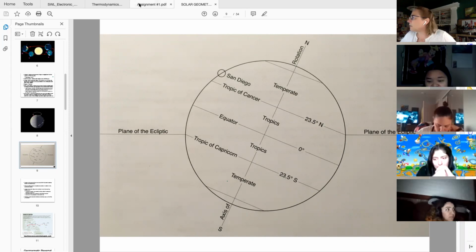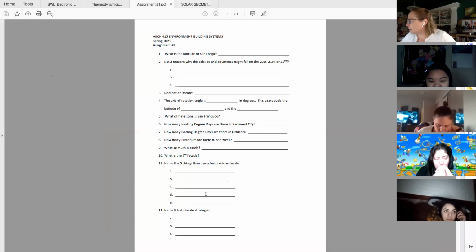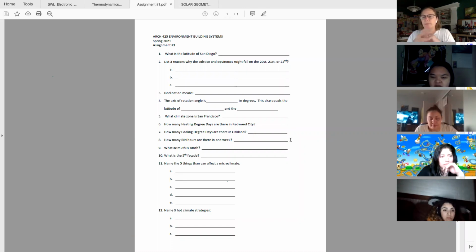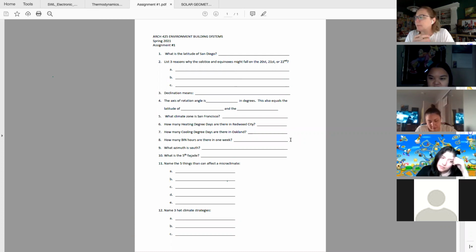I had a question about number 8. How are we supposed to calculate bin hours again? I assumed it was 24 hours times the day it asked, but I wasn't sure if that was right. That is correct. So in a year, there's 8760 bin hours. That's 365 days times 24 hours.